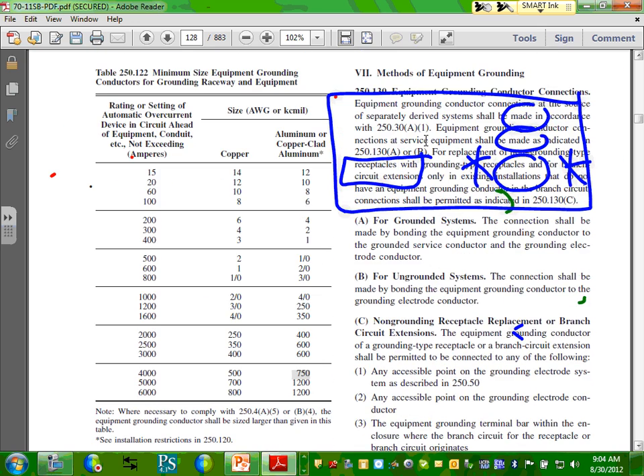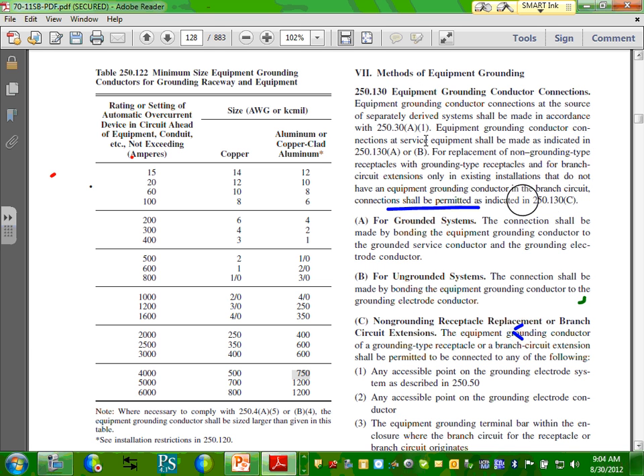That table. How many of you guys have seen this table before? You've seen it? Okay. So this table is how we size the equipment grounding conductor. Everybody knows what the equipment grounding conductor is, the ground. And why do I care? Because I'm not pulling a cable. I'm pulling a separate conductor with it. We size it based on the overcurrent protection device ahead of the circuit. What was the overcurrent protection device, Darren? 45. So let's go to 45. Where's 45? I have 15, 20, 60. So where am I going to go then?